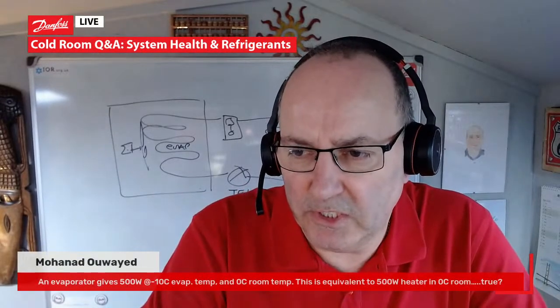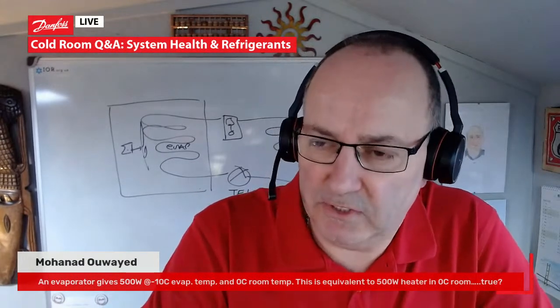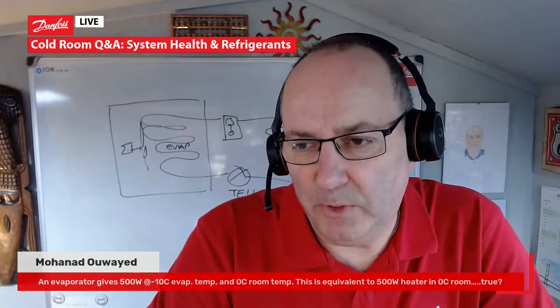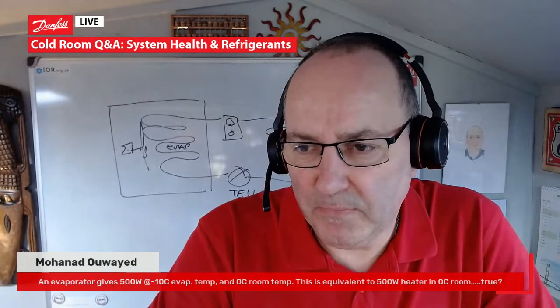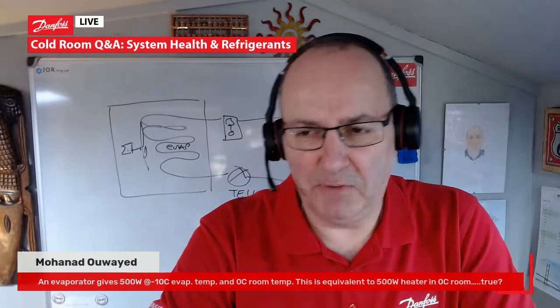An evaporator gives 500 watt at -10 evaporating temperature in a 0 degrees C room. This is equivalent to a 500 watt heater in a... Yeah, that's a brain teaser, isn't it? An evaporator gives 500 watts at -10 in a 0 degrees C room. So we've got a 10K TD on the coil. This is equivalent to a 500 watt heater in a 0 degrees C room. Yeah, that's a bit of a brain teaser. I don't know. We'll have to think about that one.